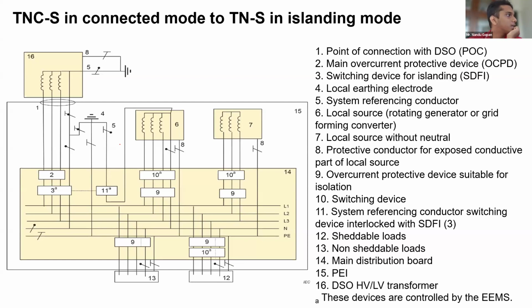So what happens is, in this, 16 is the Discom's HV transformer. The 15, meaning this whole area, is the prosumer's installation, PEI, prosumer electrical installation. And this part is the main distribution board. Mostly the changeover of the system referencing conductor happens in 14. Once again, it happens in 14. And what happens here is, from the discom transformer, the supply is coming to the distribution board.